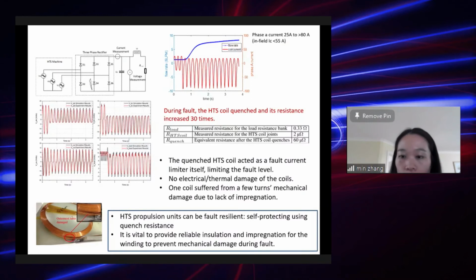So there's a self-protecting function if we use the quench resistance of this tape and choose the copper stabilized layer thickness nicely. But it's vital to provide a reliable insulation and impregnation for its mechanical support, because these windings can suffer from mechanical damage during fault. So that's the lesson we learned from this test.